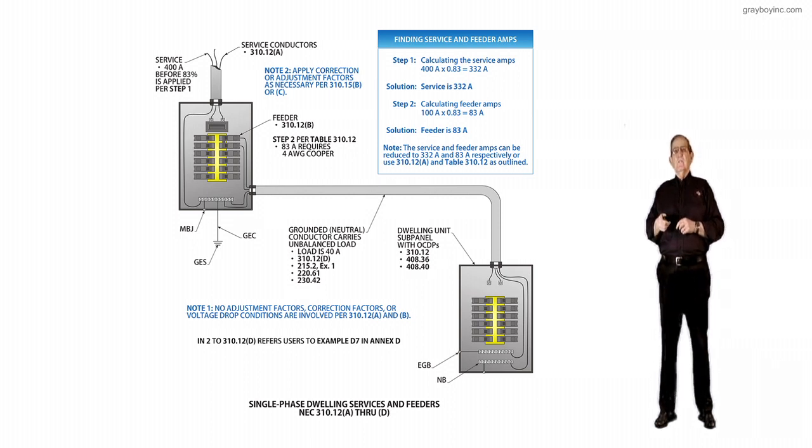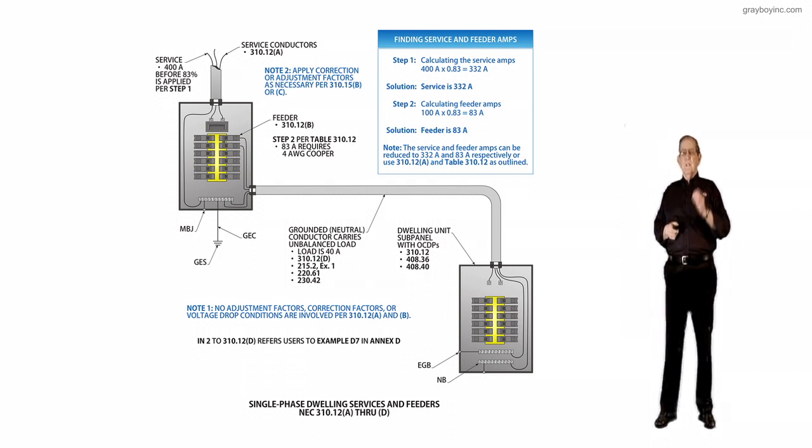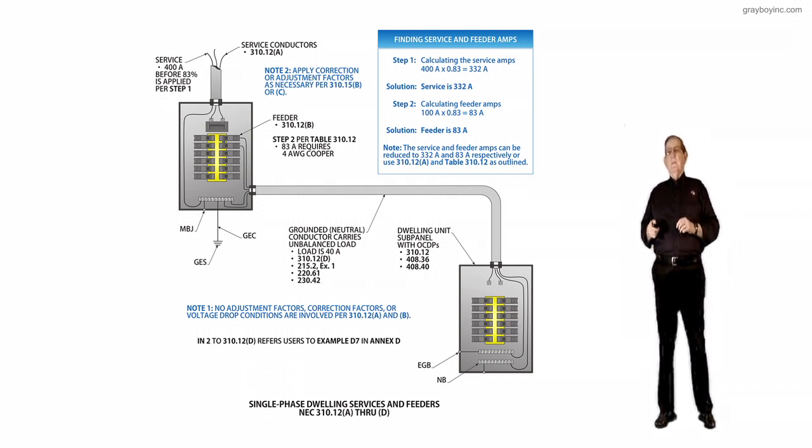Now notice that at the service equipment, everything is bonded together and connected to earth ground. The grounded conductor comes in from the service conductors, connects to the grounded bar, all your equipment grounds and neutral connect there, and it's connected to earth, and it's a common bar. But now notice in the sub panel, you've got two bars.